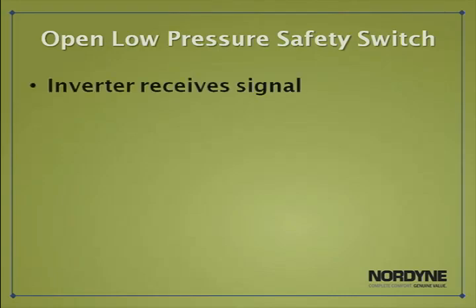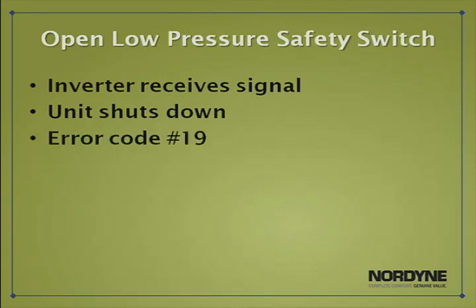The high pressure safety switch is wired in series from the inverter board to the contactor. If this safety switch opens, it will break voltage to the contactor and shut down the condensing unit. The low pressure safety switch is wired into the interface control board. If this switch opens, the inverter will then receive a signal and shut the unit down. Should the low pressure safety switch open, the interface board will display an error code number 19. Should the switch close, the unit will attempt to restart.